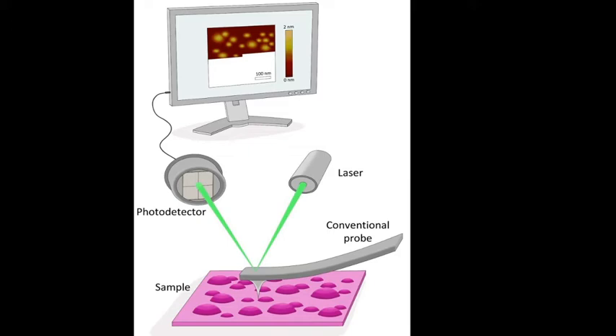The main principle behind atomic force microscopy is that in this method a laser beam is focused on the back of a cantilever that moves up and down on the surface of a specimen, and the deflections of the beam are captured by a diode. That's the main principle behind atomic force microscopy. So I will repeat this. The principle is that a laser beam is focused on the back of a cantilever that moves up and down on the surface of a specimen, and the deflections of the beam are captured by a diode.